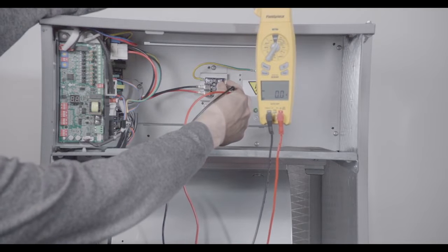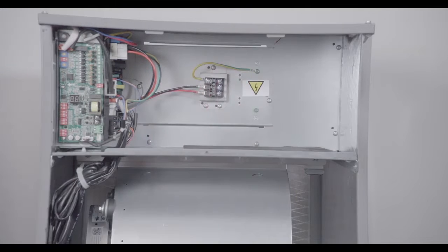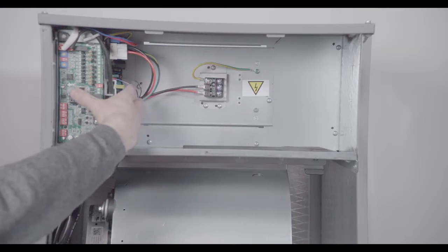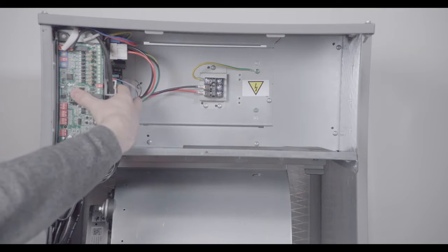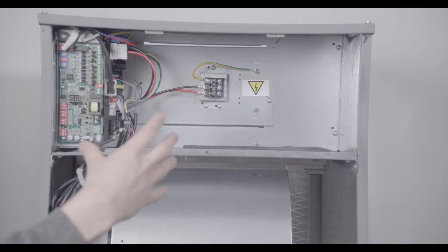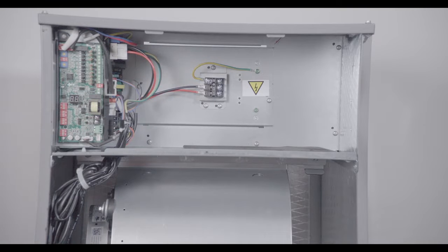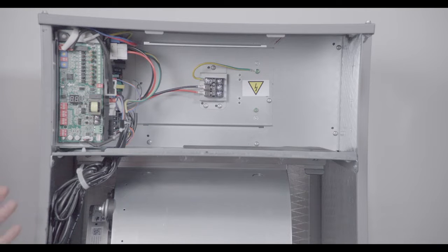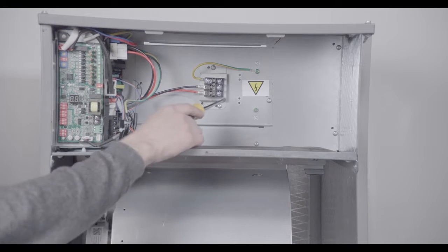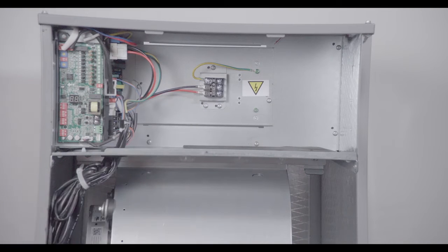The transformer we're looking for is located behind the subassembly right here, so we will need to remove the subassembly to get to it. Now, even though we have turned off our breaker and tested for zero voltage, we still need to wait five to ten minutes for any lingering DC voltage to dissipate from the board.